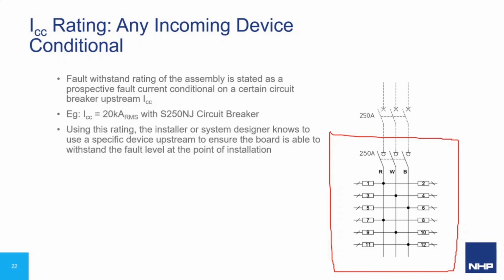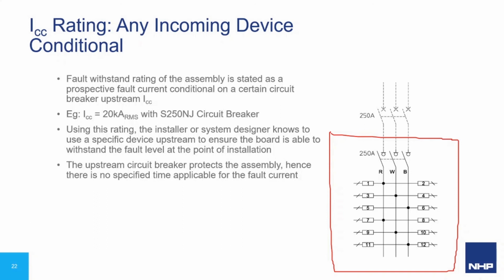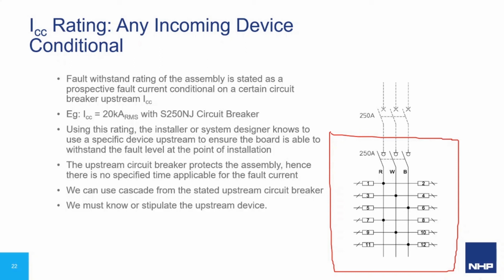Using this rating, the installer or system designer knows to use a specific device upstream to ensure the board is able to withstand the fault level at the point of the installation. The upstream circuit breaker protects the assembly, hence there is no specified time applicable for the fault current. We can use cascading of the stated upstream circuit breaker for our internal devices. The main point here is that we must know or stipulate the upstream device when using this rating.